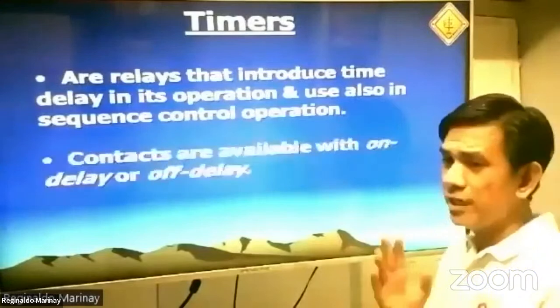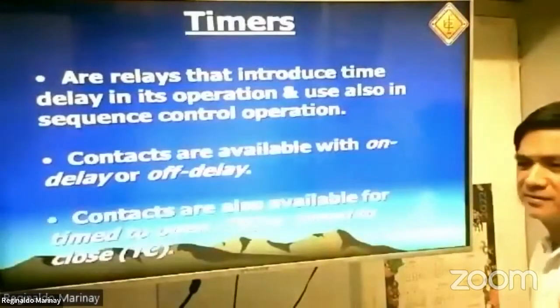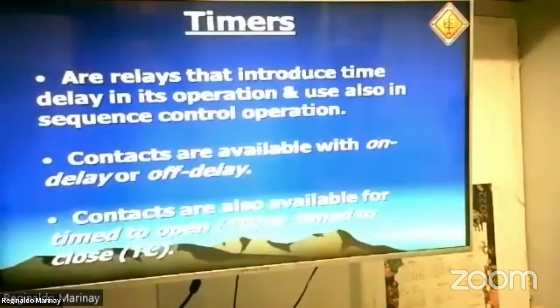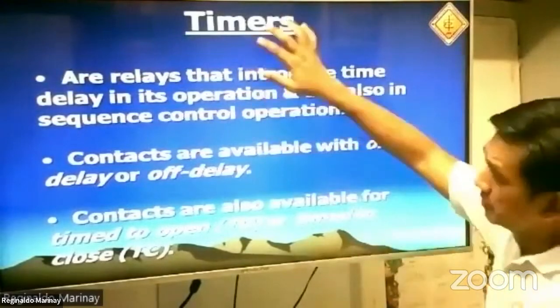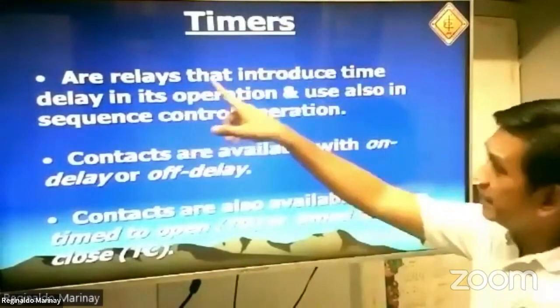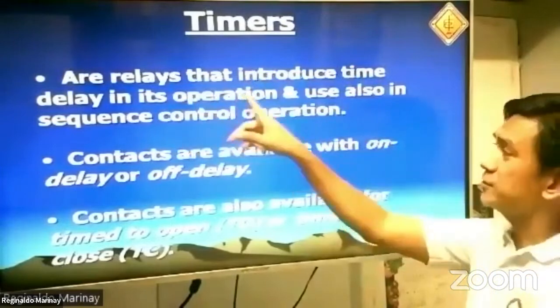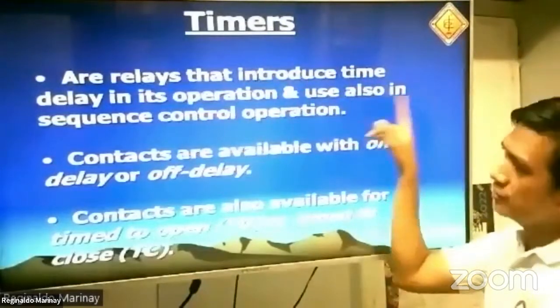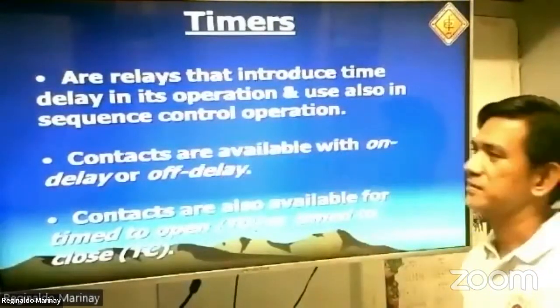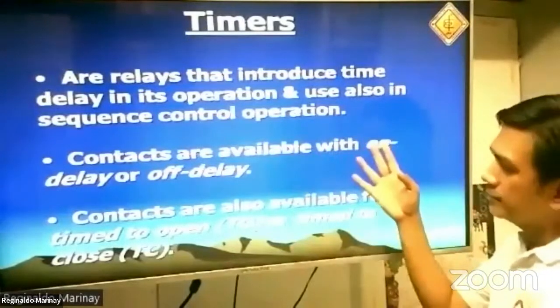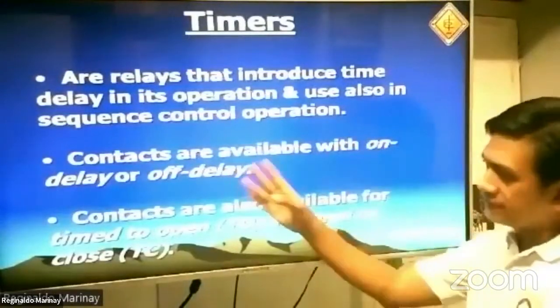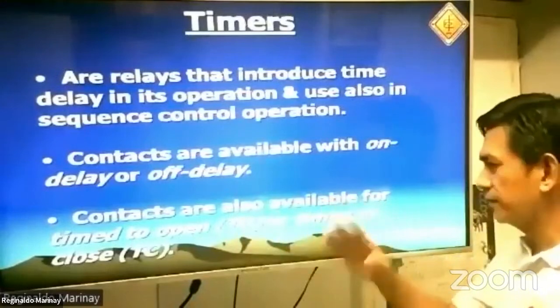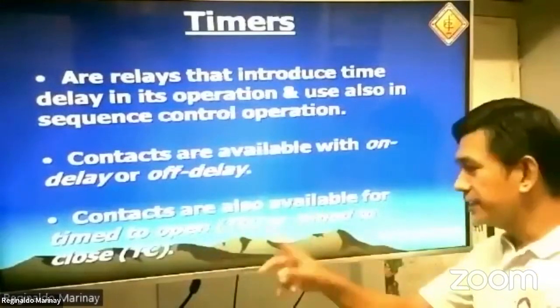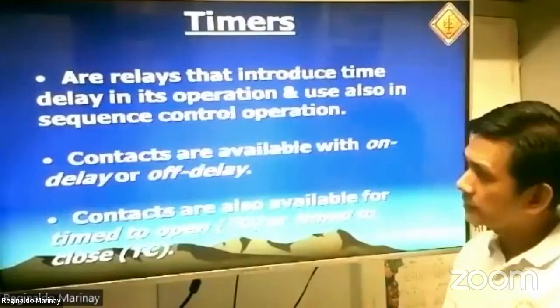Let's take a look here. Let's go now to the timing relay. Let's take a look at the timing relay. What are timers or timing relays? These are relays that introduce time delay in their operation and are also used in sequence control operation. Contacts are available with on delay or off delay. Contacts are also available for time to open, and then there is time to close.